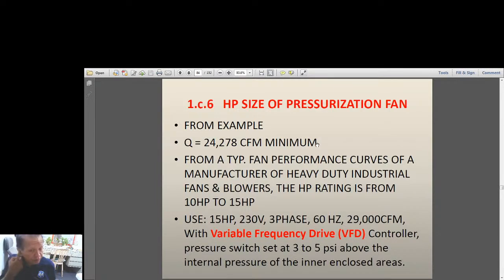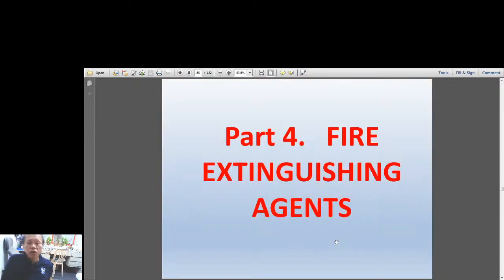Okay, and here is a way to size it up. I already indicated for an 11-story building, the calculated capacity of the fan is 24,278 CFM, and the fan was selected at 29,000 cubic feet per minute, and it is driven by a 15 horsepower motor and controlled by variable frequency drive. Okay, so the pressurization fan maintains something like 3 to 5 psi pressure, a little higher than the pressure inside the burning room. Okay, now we go to fire extinguishing agents.